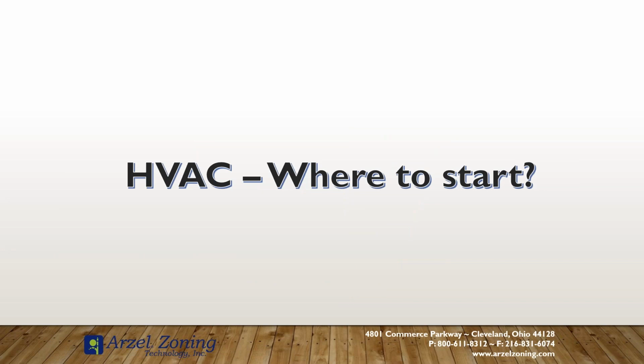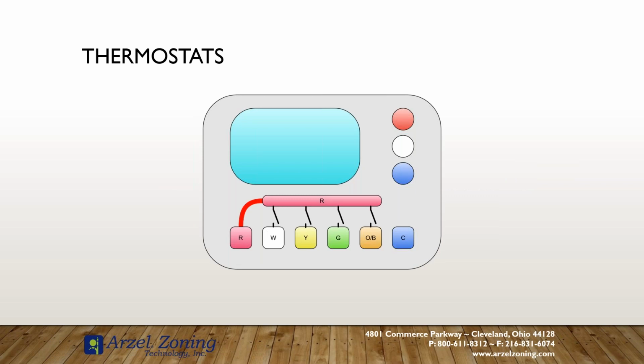So when we start diagnosing our HVAC system, and we're probably going to burn through this faster than the 2 hours, but when we start testing our HVAC system, we always start at our thermostat. Now there's a lot of things that will tell us our thermostat is running, but if things aren't running, our thermostat's the place to start. And technicians, as they become more experienced, will be able to skip some of these steps, but it's good to know the basics. It's really good to go back to the basics, because when we have a compounding problem, we need to be able to know what is or isn't working so that we can diagnose as many of the potential failures as possible.